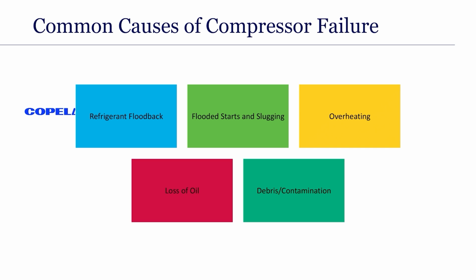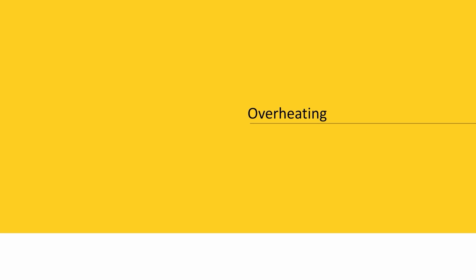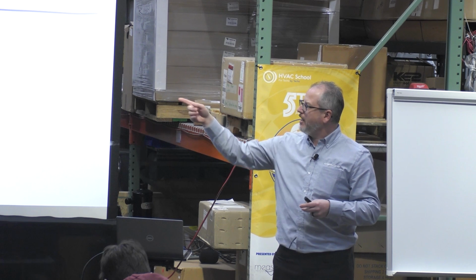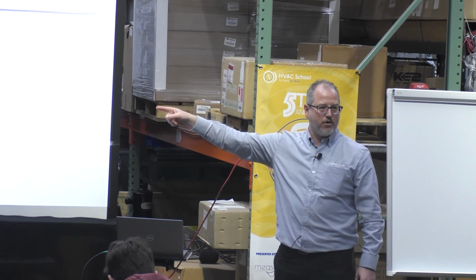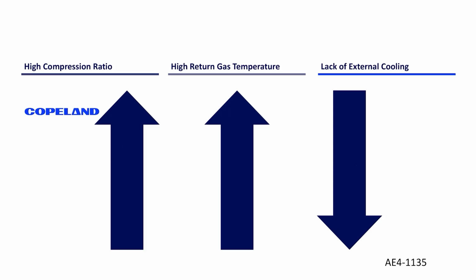So these are all the different common causes of failure, but today we're just concentrating on the overheating part. When we have a high compression ratio, that compressor is going to be overheating. Without even taking out our thermometer, we have our pressures. We just add 15 and divide those, and we're going to come up with the number, right? It takes less than a minute to figure that out. And without that temperature probe, you're going to know if that compressor is overworking, if there's a system problem somewhere. You're going to have to be looking somewhere.